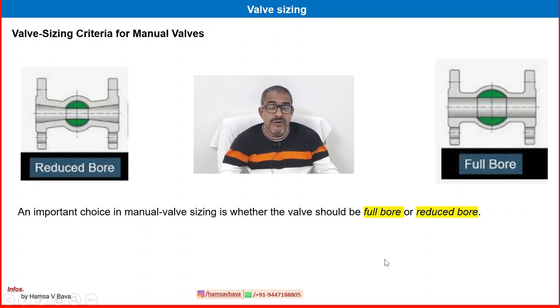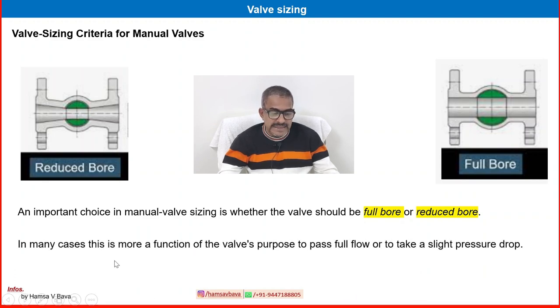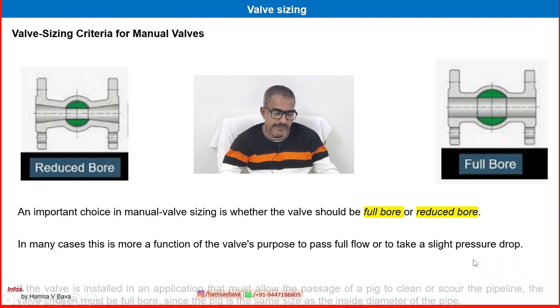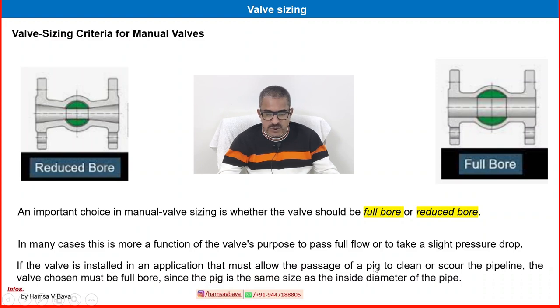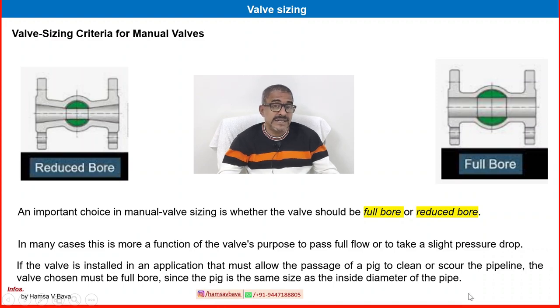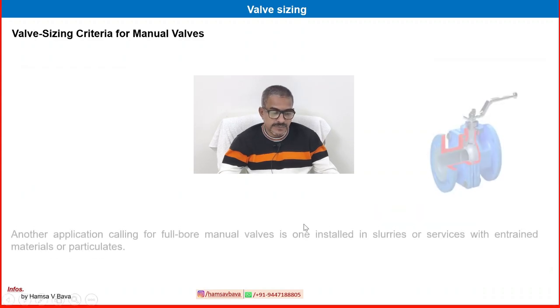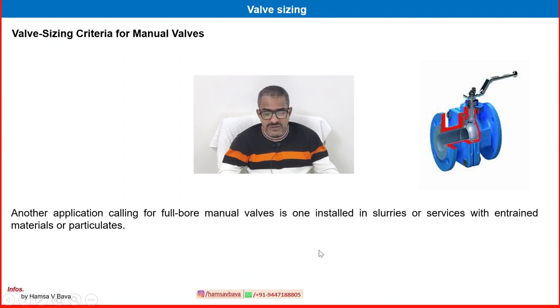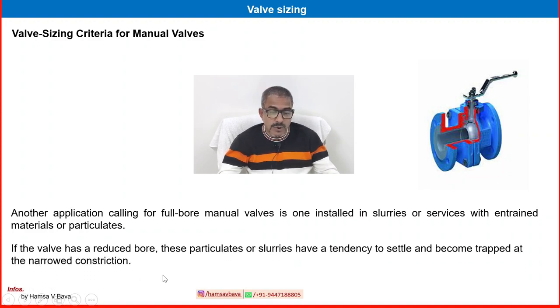Selection of a manual valve for a particular application is more a function of the valve's purpose — to pass full flow or to take a slight pressure drop. If the valve is installed in an application that must allow the passage of a pig — used for internal cleaning of a pipeline — the valve chosen must be full bore, since the pig is the same size as the inside diameter of the pipe.